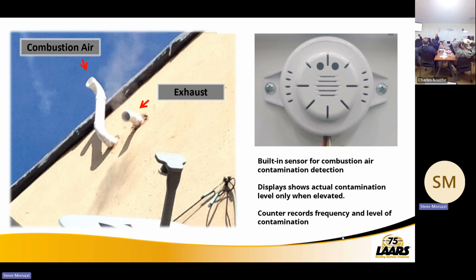All right, so again, that flue gas recirculation, built-in sensor, so the display will actually show the contamination levels when it's elevated above the value. And our example was 8,000 parts per million of CO2. You can adjust that. You want to drop that all the way down to 2,000 parts, you go ahead. So that'll appear on the display, and it will also record the levels of contamination. So when I talked earlier today about different percentages, maybe it's only contaminating 10% of the time or 20% of the time versus 80 or 100% of the time. So it'll record those levels right on the display, and you can get in and read that as well.